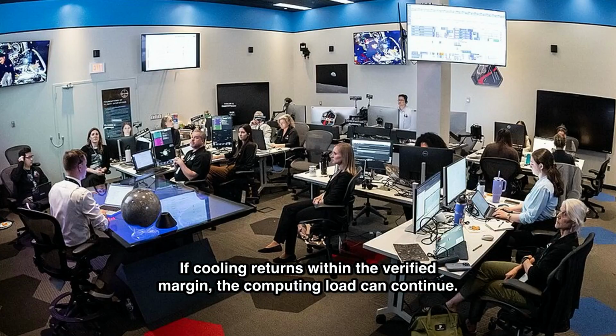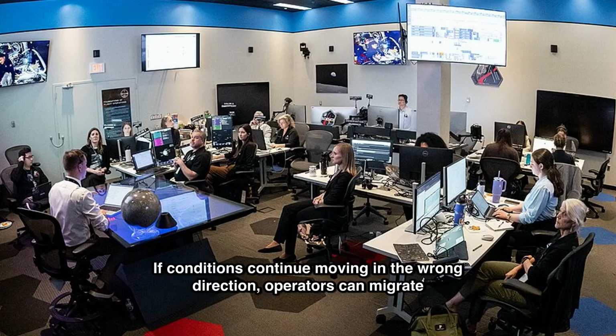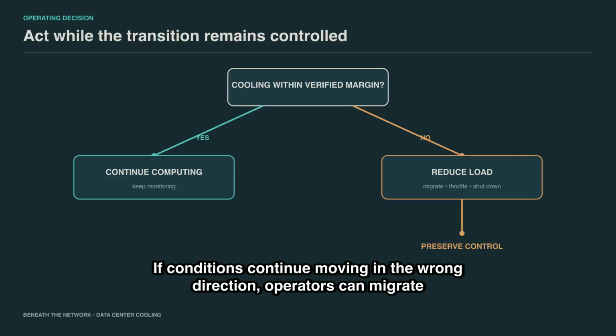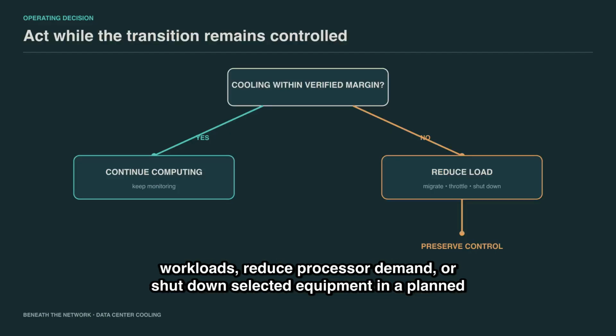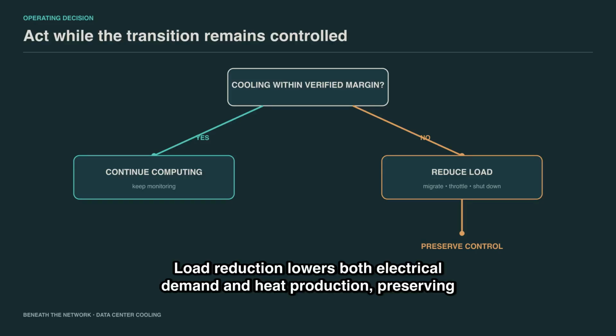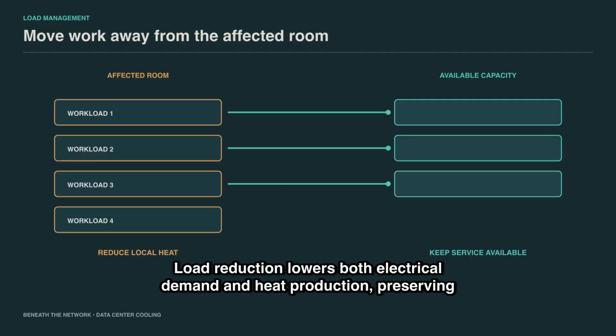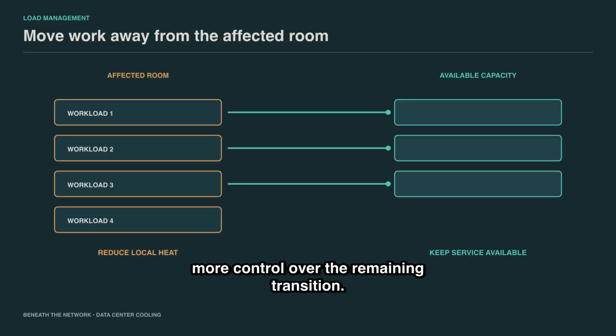If cooling returns within the verified margin, the computing load can continue. If conditions continue moving in the wrong direction, operators can migrate workloads, reduce processor demand, or shut down selected equipment in a planned order. Load reduction lowers both electrical demand and heat production, preserving more control over the remaining transition.